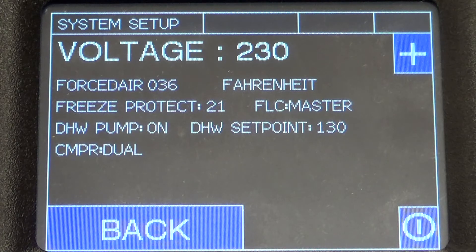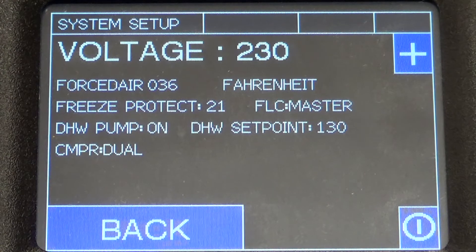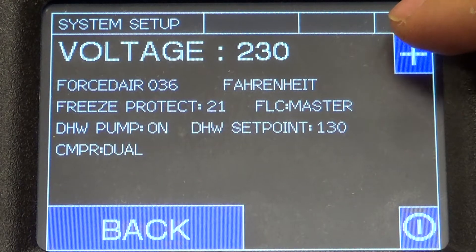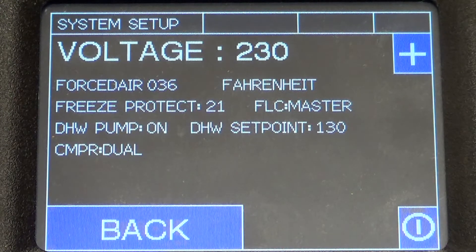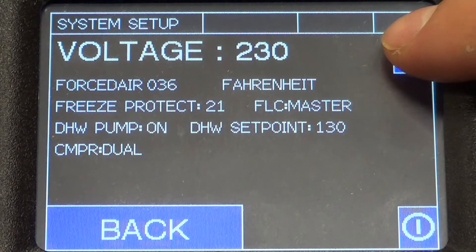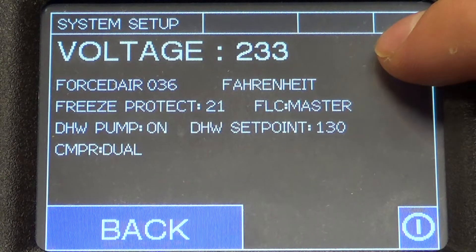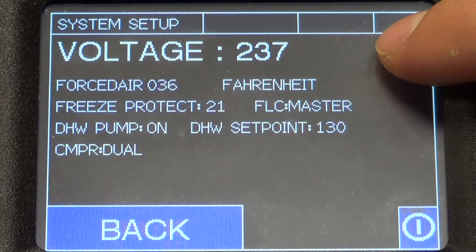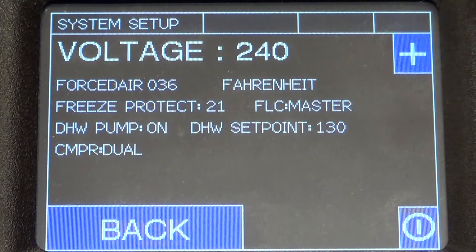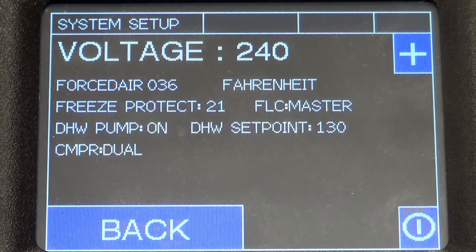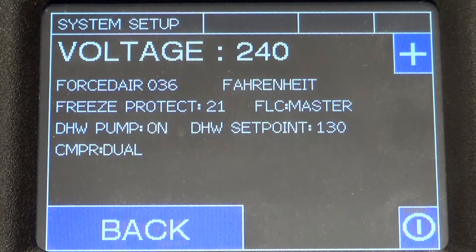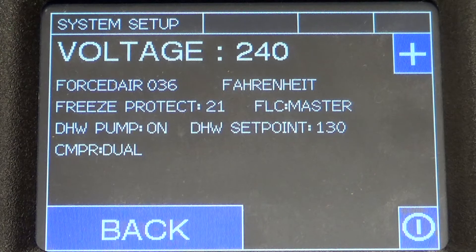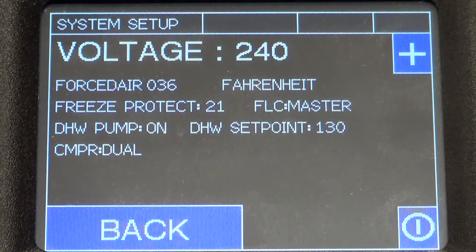Another innovative feature of the ORB is real-time EER monitoring. To enable this, the voltage needs to be inputted. Typically once it's started up, the contractor would take a voltage reading at the incoming terminals with a multimeter and enter it here. Let's say 240 volts. Once the ORB knows that 240 volts is coming in, it monitors the amps and calculates real-time EER based on those conditions.